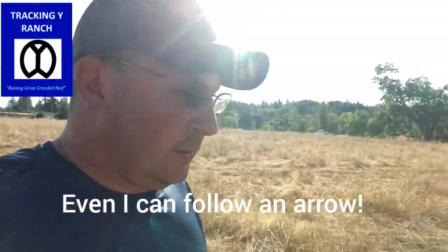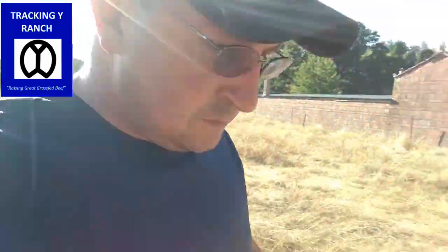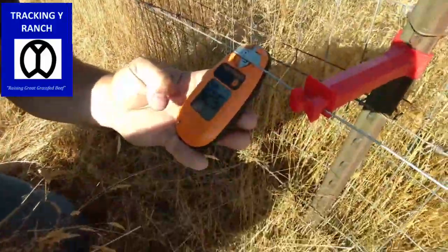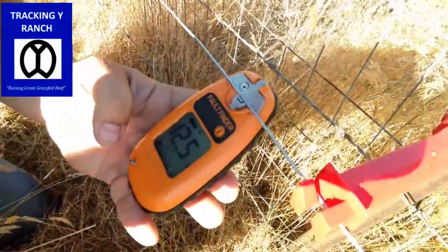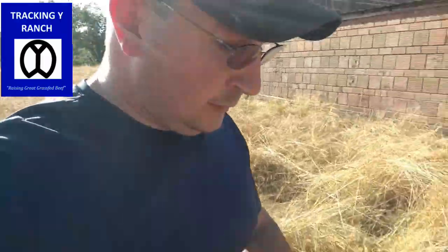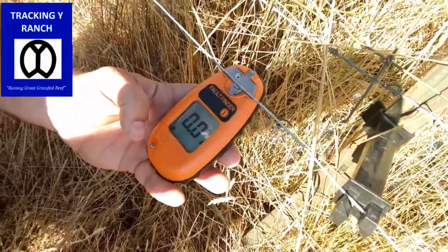So we're going to follow that arrow — go down here to the left. I'm going to go two insulators down and put it here. It's reading 13, 12.8 amps, still pointing to the left. That's the great joy of this tool — it's going to point you in the direction of your fault and help you figure it out. I'm going to bounce two more insulators down, put it on, and now it's reading zero. So zero amps — it's got to be back between the last test and this one.